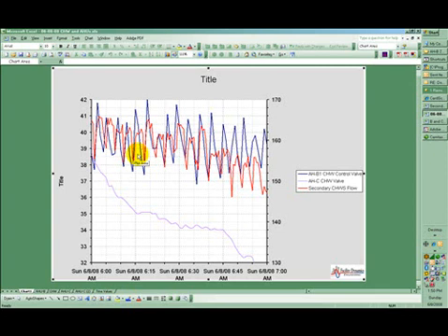So that's another reason we need to fix this. Even if it isn't the exact cause of the chiller trip, which I think it could be at least some of the time, we still need to fix it to have longevity of the valve actuator and packings. Thanks. I'll post this on the website along with the spreadsheets and create an action item.